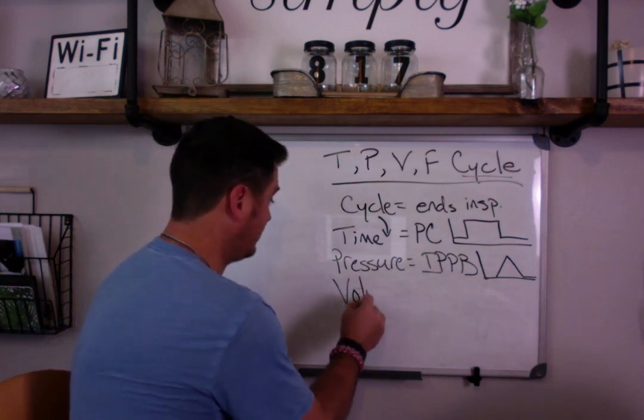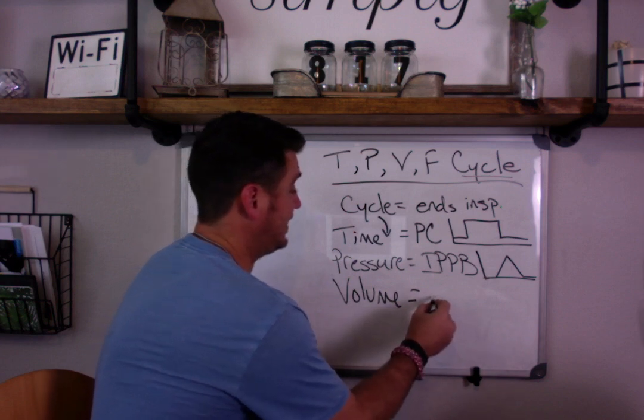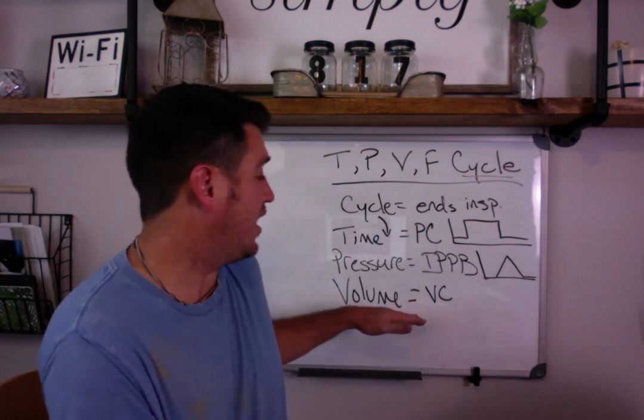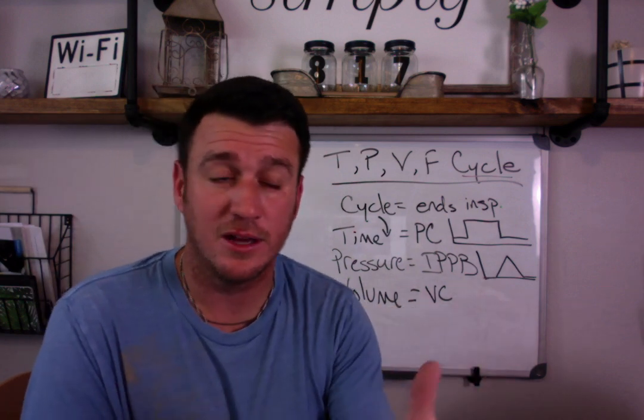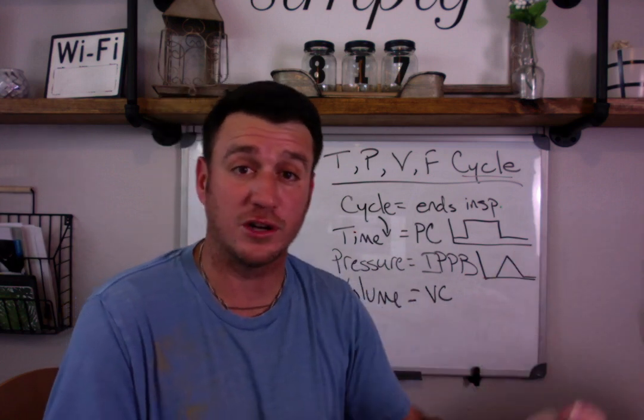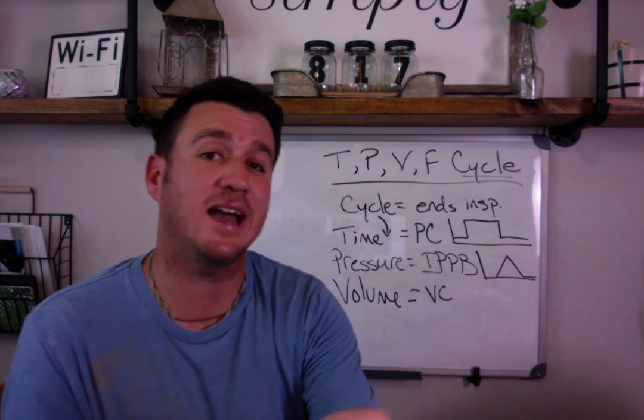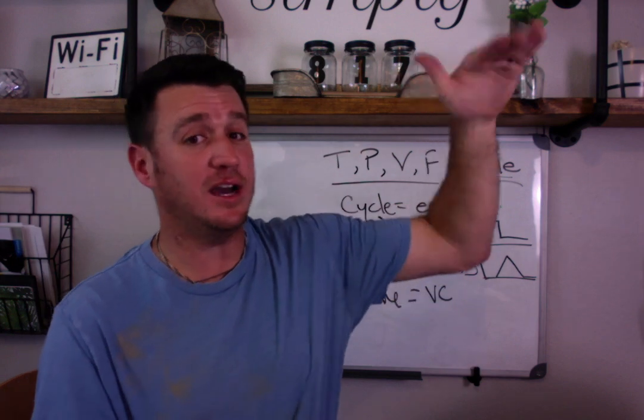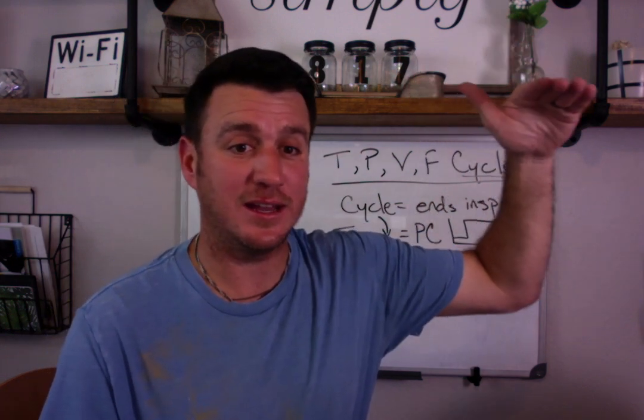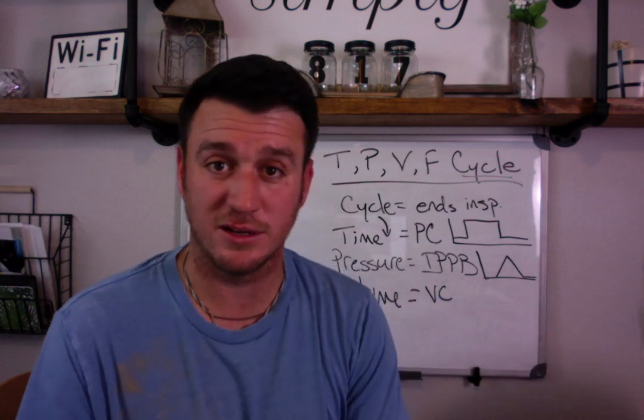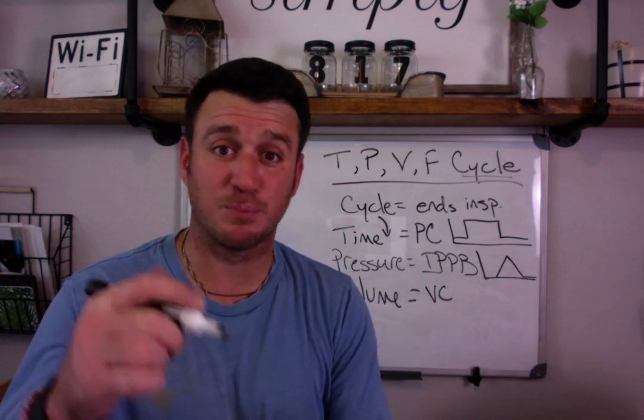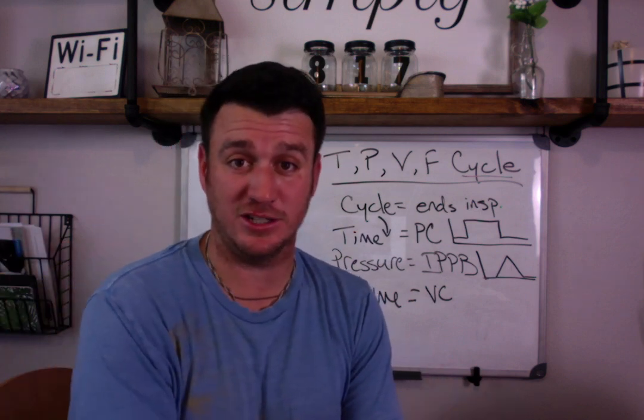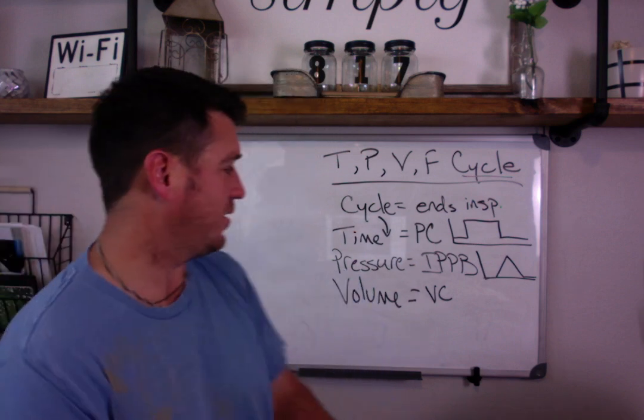The next one is volume cycling, which applies to your volume control modes — VC-AC, VC-SIMV — they all operate on volume. You tell the ventilator to give a tidal volume of 450 milliliters; you don't set a pressure, you set a tidal volume. The vent delivers 450 mL, and when it's done, it cuts off and allows the patient to exhale. When this preset volume is reached, it cycles into exhalation and does not give more than the set tidal volume.